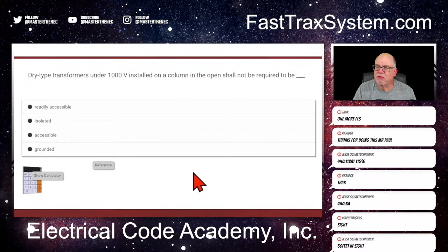What do you think? Now, where do you go in the code? Well, the first dead giveaway for me, and for you if you're preparing for an exam, is right here. Okay. The second dead giveaway for me is it's a dry type. So we're not looking for oil filled. We're at a dry type, right? And we're trying to use these words to determine what we're talking about for this transformer. So in a transformer, you know what article transformers are.